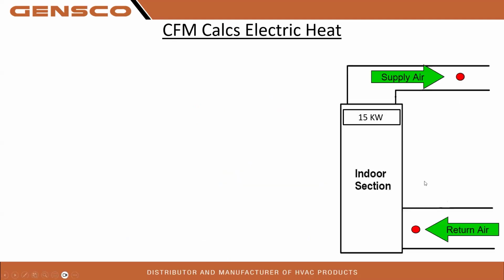I love it. CFM calcs with electric heat, right? So you got your supply air, got your return air, right? Of course, these should be taken at the unit. If we're taking this at the register, there could be infiltration. We could have some heat loss through the ductwork. Of course, when we start up the systems, we got to warm up all that ductwork or cool down the ductwork. Return airs, you could have multiple return airs. You could have an outside air that's open. So we need the actual air at the indoor unit.